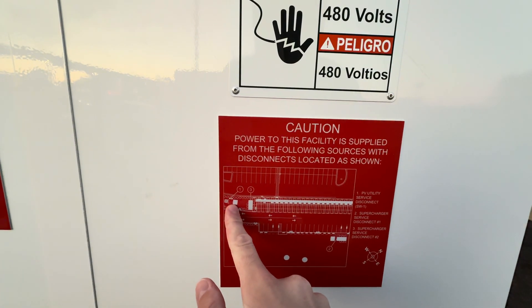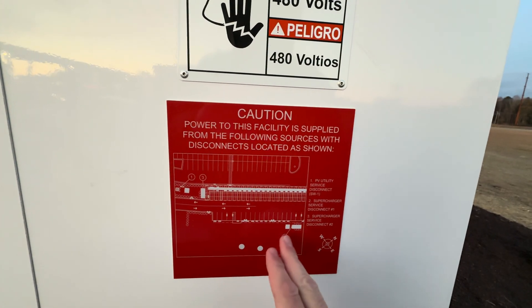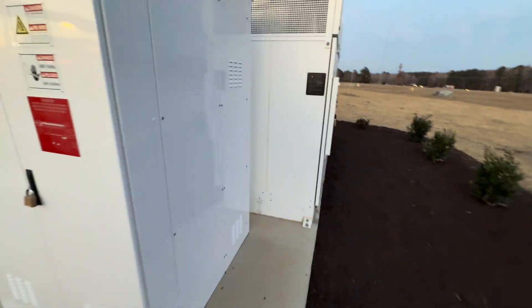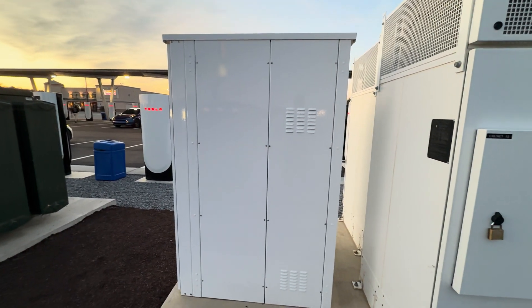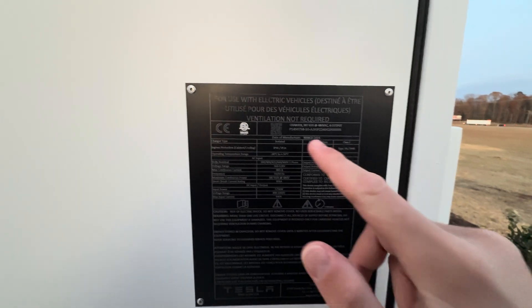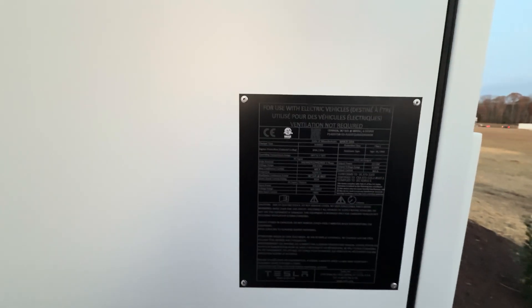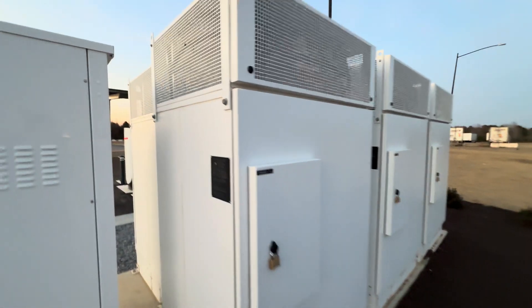That's where we started — that's the main transformer. And then that's the photovoltaic or solar system hookup. So we're now at supercharger service disconnect number one. 3,000 amps here — pretty deep switchboard. That might be a custom enclosure, actually. Here we have cabinet 15. These are just standard version 3.5 supercharger cabinets. As always, 387 kVA, 250 kilowatts. And these cannot do 1,000 volt — it's zero to 500 volts right there. Typical version 3 output.